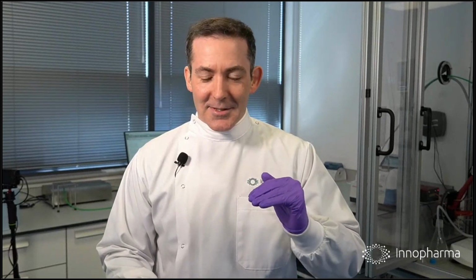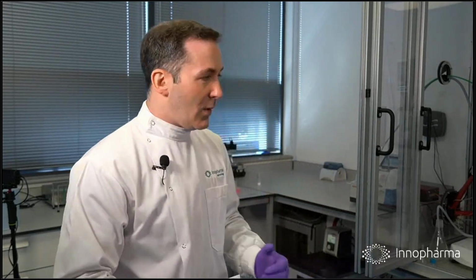So what we're seeing here is over 16 seconds, 16 samples are collected. There is some processing that has to be done. We'll cover that in a while, and so on. So capture, measure, release, and recycle in seconds, exactly. But in fact, what I should say is that the detection is happening just by delivering light and capturing the light. So rather than extracting a sample from the process and measuring it and returning it to the process, that's why we have our probes directly positioned into the process.